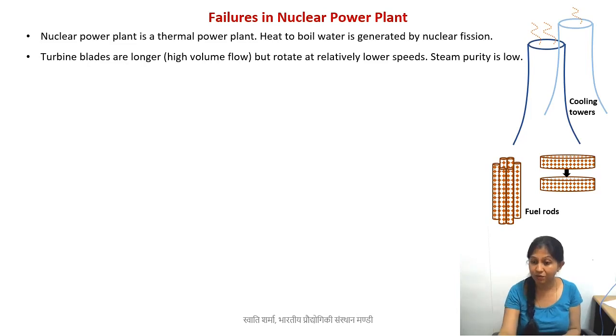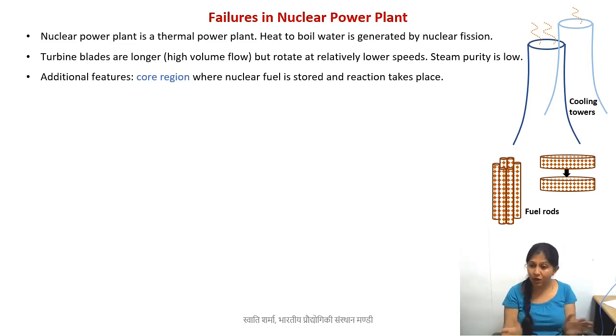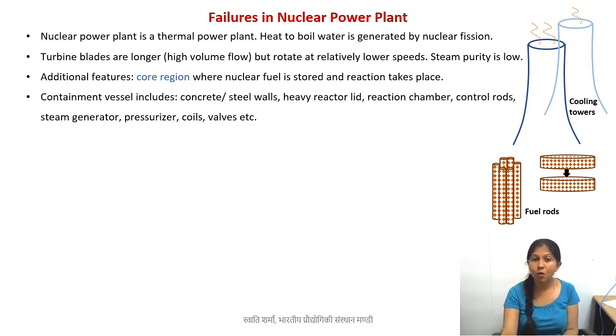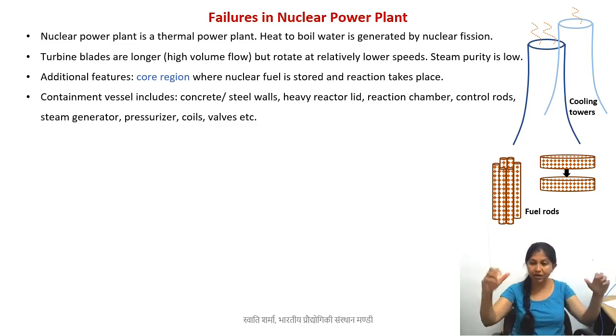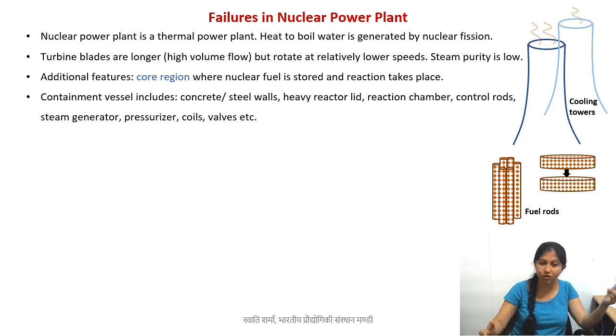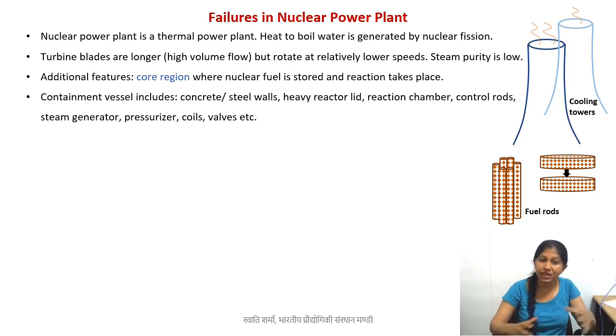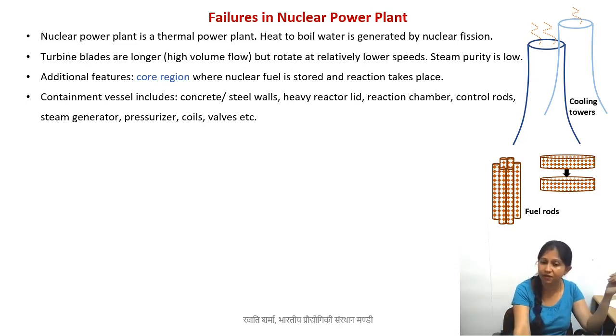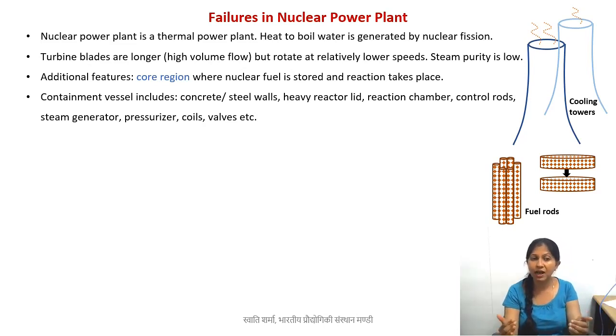The place where the reaction takes place has to be really strong. The chamber or vessel where the fuel goes — where the primary reaction takes place, known as the core region — is made of very strong steel-reinforced concrete walls. It also has a very heavy lid on top that can weigh a couple of tons. In addition to the fuel rods, there are also control rods, which are there to control the reaction and are made of materials that can absorb neutrons. We also have the steam generator inside the chamber, and in pressurized water reactors there are also pressurizers, different coils, different valves — all inside this strong containment vessel.